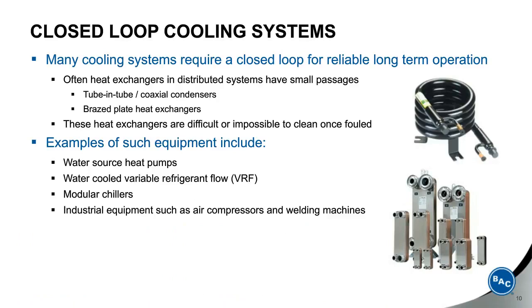Now, many cooling systems require a closed loop for reliable long-term operation. Often, heat exchangers in distributed systems have small passages. This includes tube-in-tube / coaxial condensers, brazed plate heat exchangers, and these heat exchangers are difficult or impossible to clean once fouled. Examples of such equipment include water source heat pumps, water-cooled variable refrigerant flow systems, modular chillers, and industrial equipment such as air compressors and welding machines.